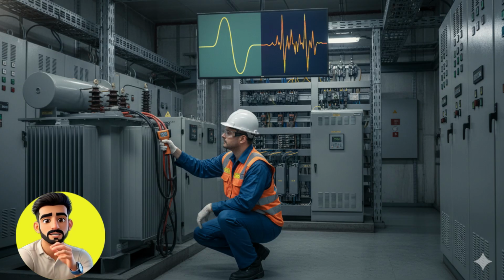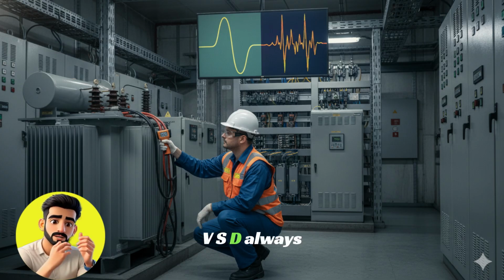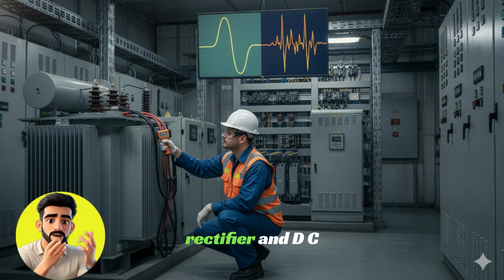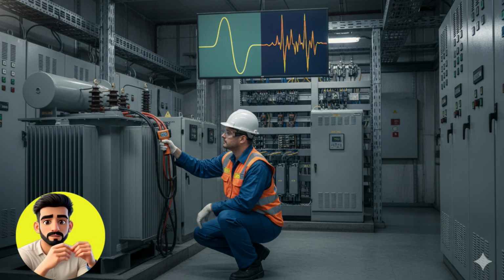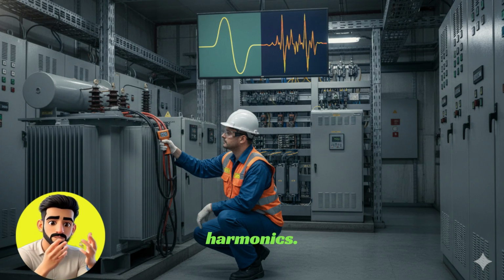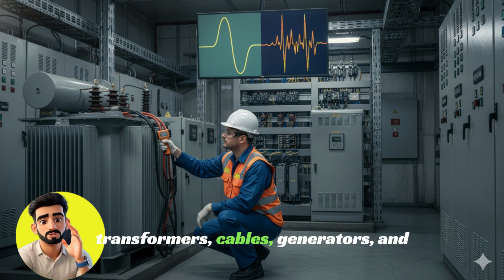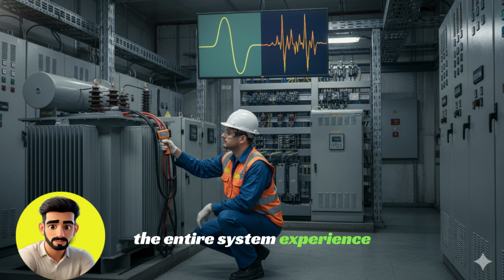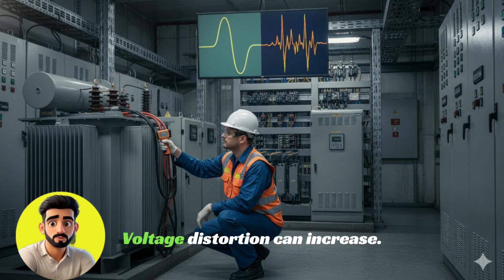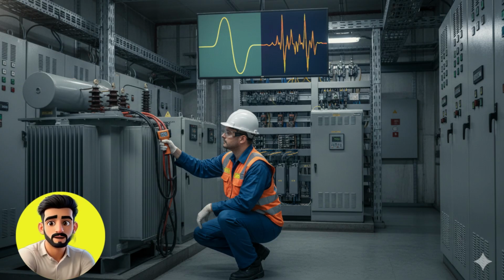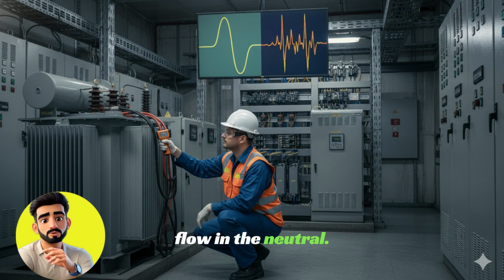The operation of VSD is different. VSD always draws power through the rectifier and DC bus. This results in continuous harmonics. Due to these harmonics, transformers, cables, generators, and the entire system experience extra heating. Voltage distortion can increase, and unwanted currents may flow in the neutral.